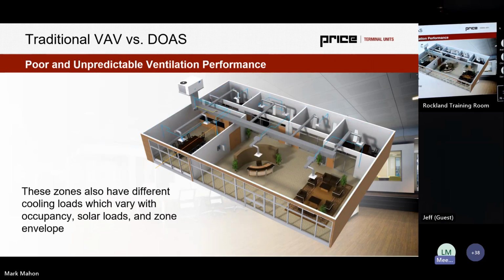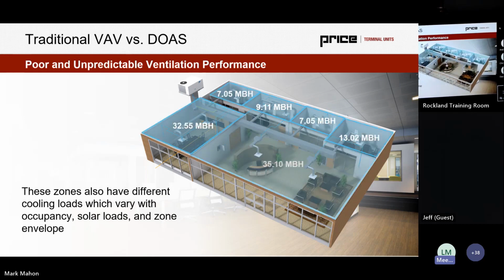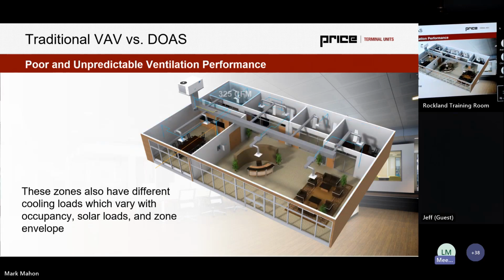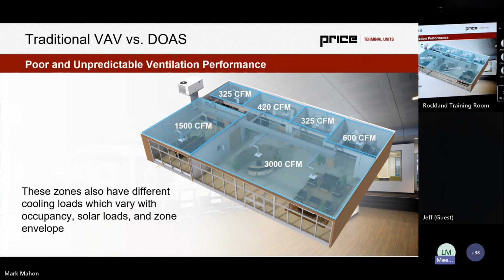Now, this same system in a VAV system is also going to have to deal with the space cooling load. And that's going to vary obviously with occupancy, solar load, zone envelope. It's going to depend also on other internal loads from the electrical system, from lighting, from equipment that we may have in the space. And this same MBH per zone is going to be taken care of by air only. So the airflows I have on screen here are assuming a 55-degree saturated supply temperature for design day, and that's how much CFM we're actually going to need to reach the load of each zone.